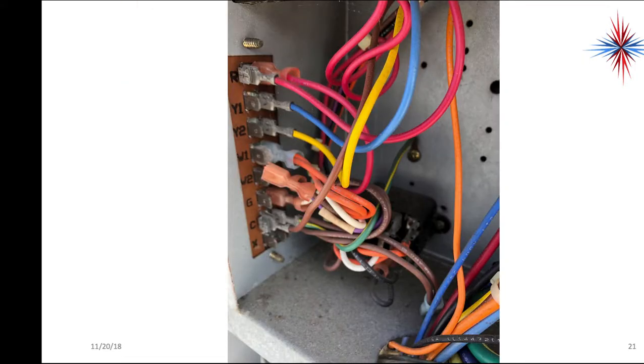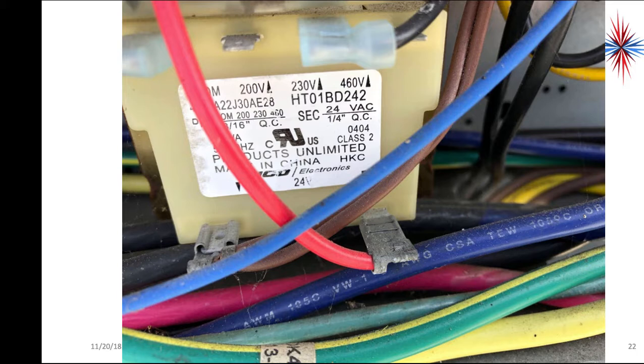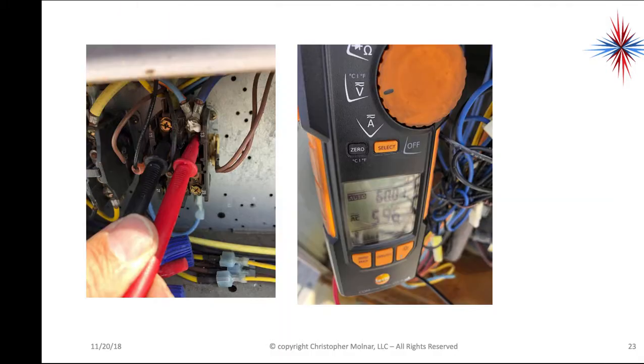So we come over here, take a look at the blower relay, which is hiding out in the back here. Nothing magical there. Everything's connected, including Y1 and Y2 on the terminal strip. W2 is disconnected, but that's been jumped someplace else at the unit. Okay, take a look at the transformer. Everything's wired correctly.